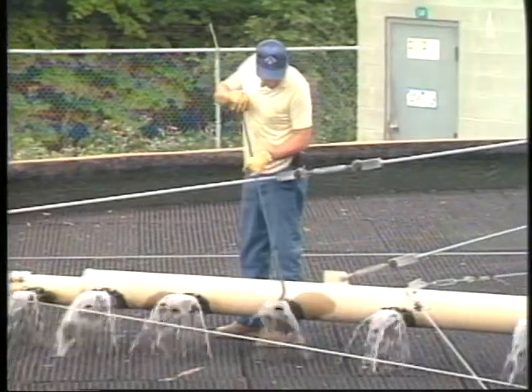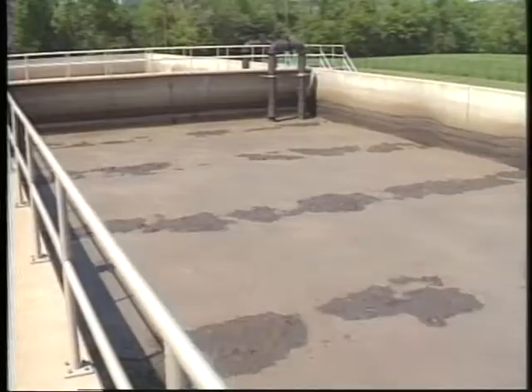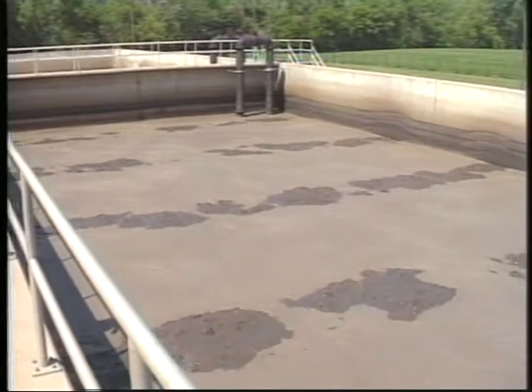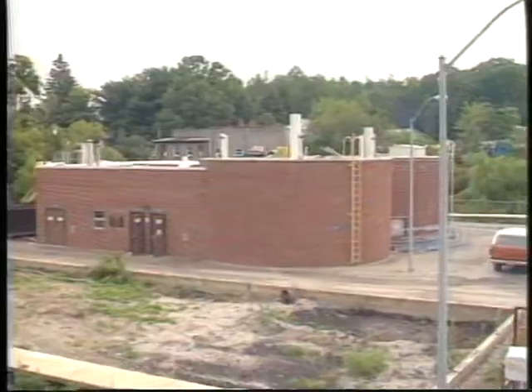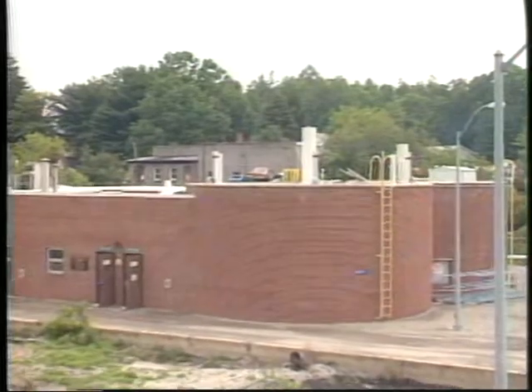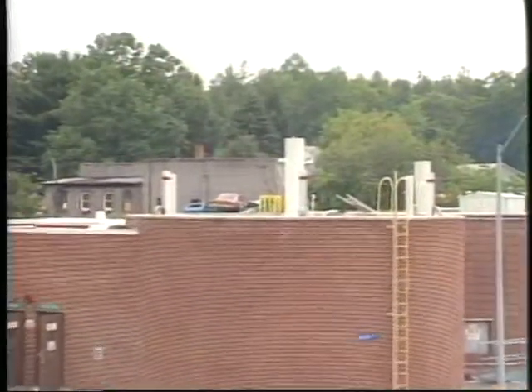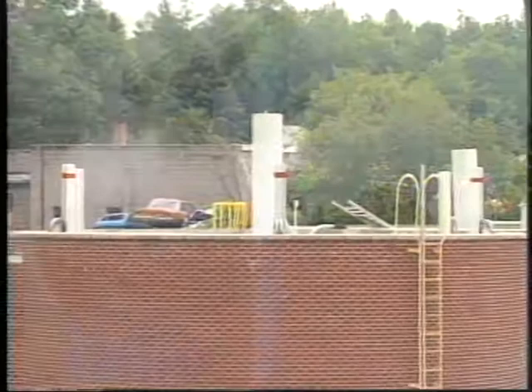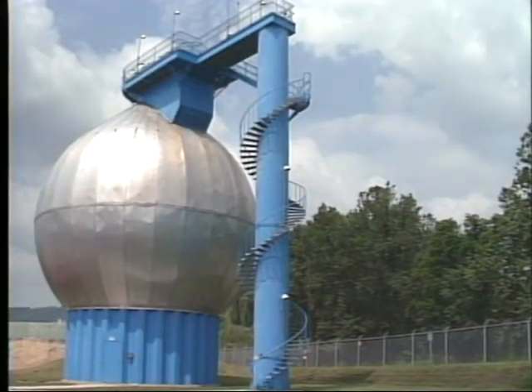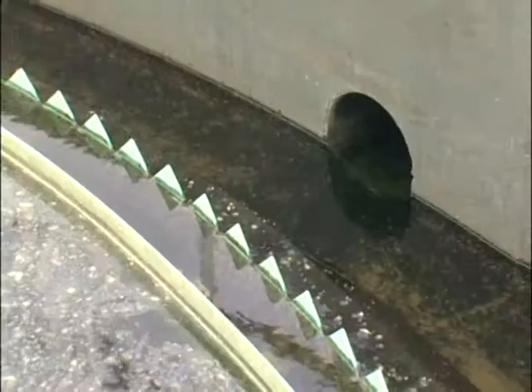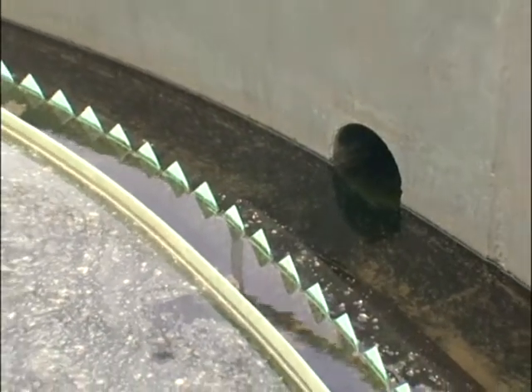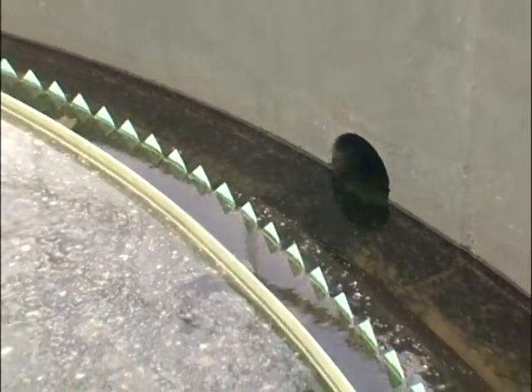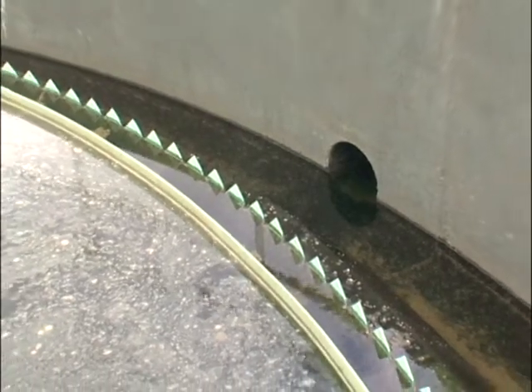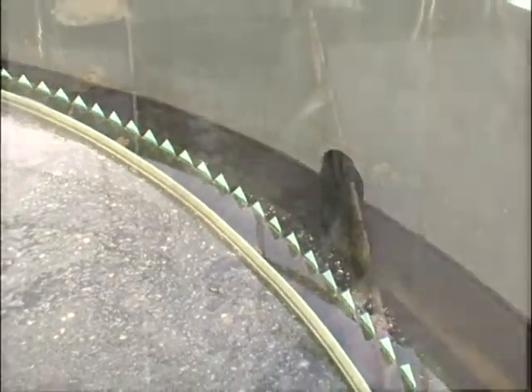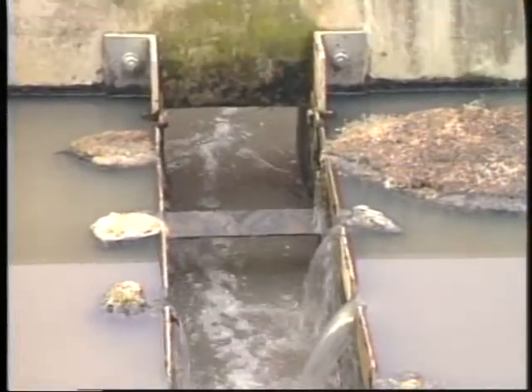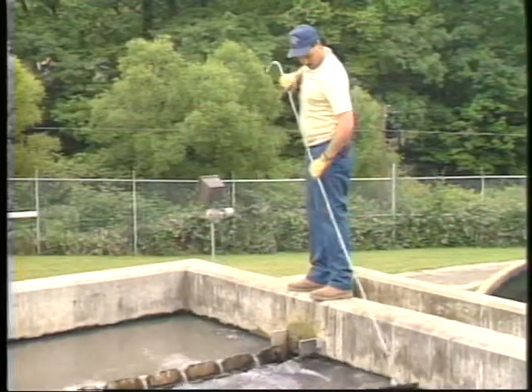Disposal of the floatable solids can be a problem as well. In many cases, floatable solids are placed in an aerobic or anaerobic digester. These solids present a particular problem in anaerobic digesters because they increase the depth of the scum blanket, resulting in the loss of valuable digester space. The effluent weirs should be level and clean, allowing an even flow of wastewater to discharge over the entire course of the weirs. Measures should be taken immediately if weirs are uneven, clogged with solids, or become leaky.